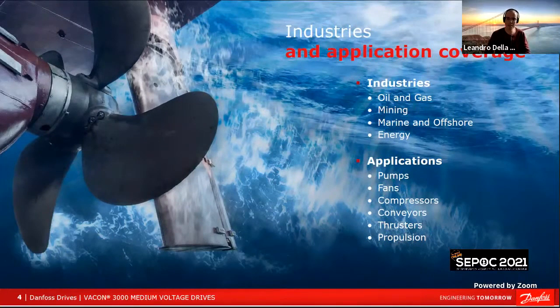And of course these products are still under development, meaning we have goals to reach higher levels of power. The highest we can provide today is 7 megawatt, but very soon we will be offering also 11 megawatt drives. Still the design is extremely compact, because we allow lower power drives to be combined in parallel. Inputs are connected in parallel, outputs are connected in parallel, in a way that the customer can still control them as a single drive, meaning just one control unit acting upon all the power stages, and still be able to have these very high power applications.